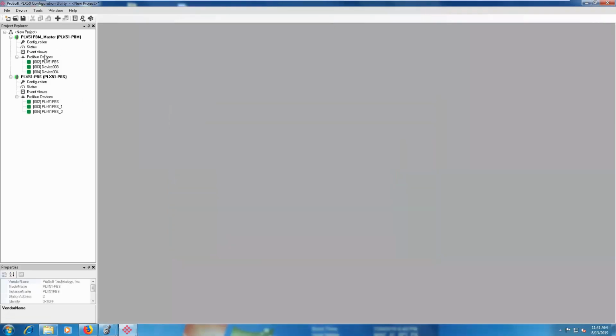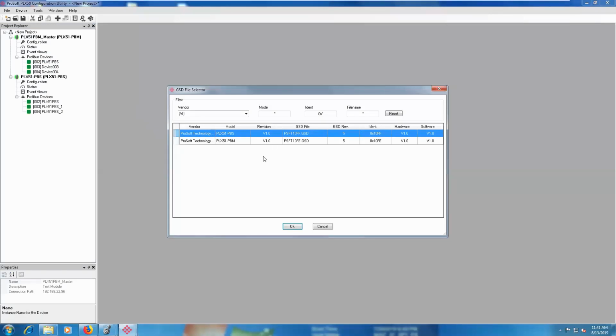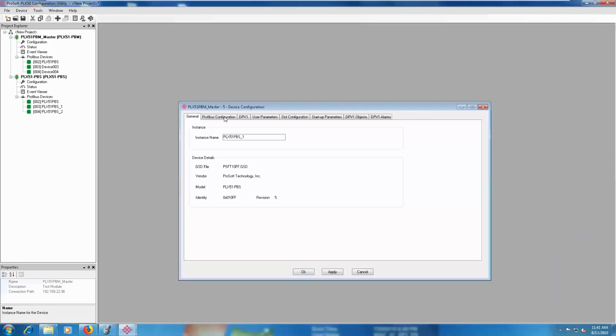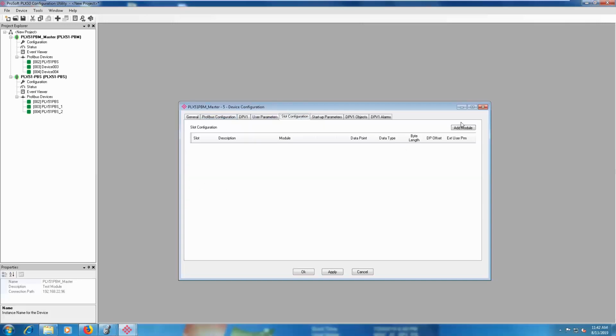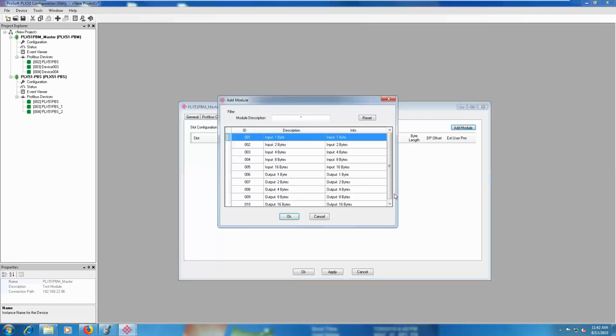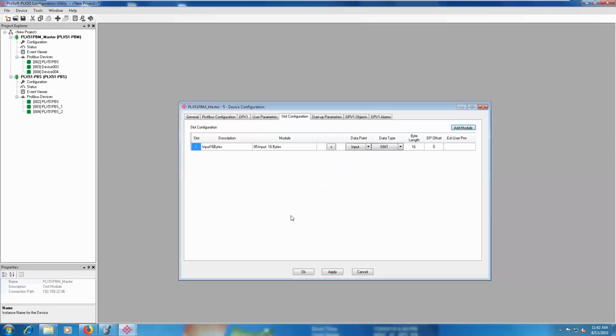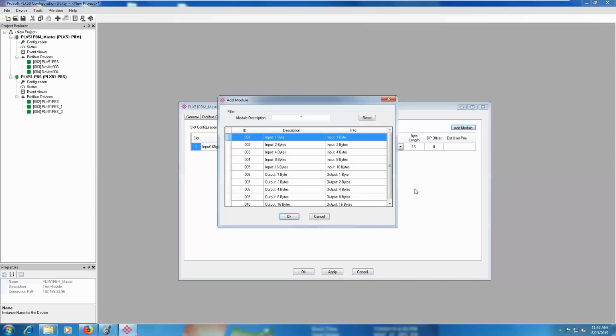As far as adding a new Profibus DP device, that's done simply by doing add Profibus DP device. You've got a device catalog which would show you all of the devices that are in your project folder. And so you would just select a device in there, add that device into the network, and then this is where you would set up your slot configuration, which is essentially where you're setting up how many bytes of input data as well as how many bytes of output data you want to exchange with the devices.